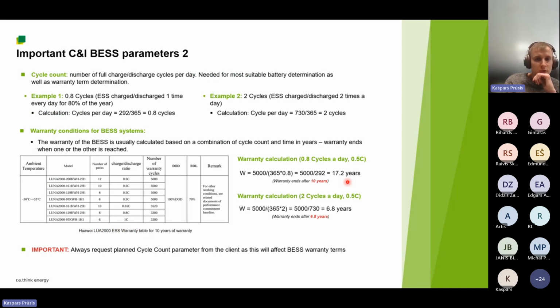On this slide, there are a couple more parameters that are important, and from which one is cycle count. And this is actually very important. And this cycle count defines the number of full charge discharge cycles per day. So this is a parameter that your clients will specify because it will determine the battery types used, as well as it has a great effect on the warranty of the system, which is also very important for commercial clients. And to illustrate this, I will give you an example.